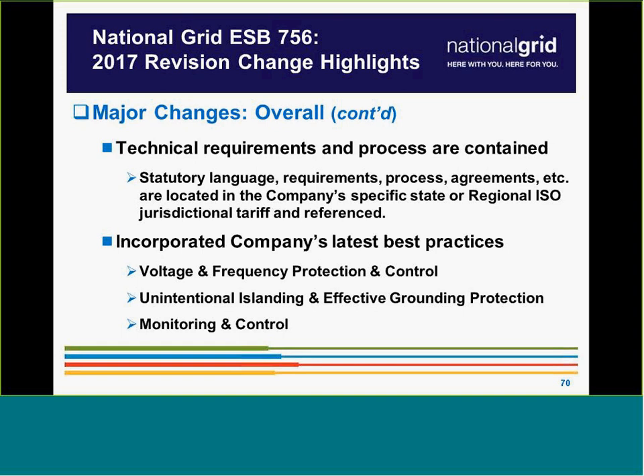You'll find there's a list of acceptable transformer configurations in the ESB. Can I get a show of hands - how many people do projects over 500 kilowatts? All right, what kind of crowd - cool. So, plan: if you're interconnecting to a distribution circuit, you need to provide for effective grounding. Your inverter typically - I haven't seen an inverter yet that can be grounded on its own, just connecting the thing up by itself. That's just the way inverters work. You need an external ground source, whether it be your wye ground delta interconnect transformer or an external grounding bank. All of that is discussed in the ESB in the effective grounding and transformer sections.